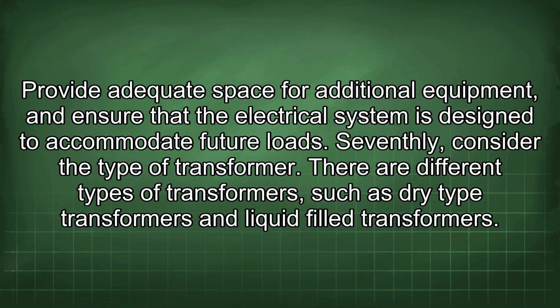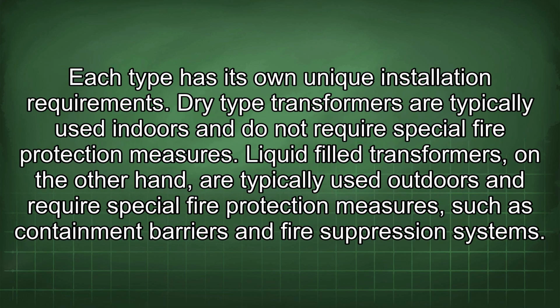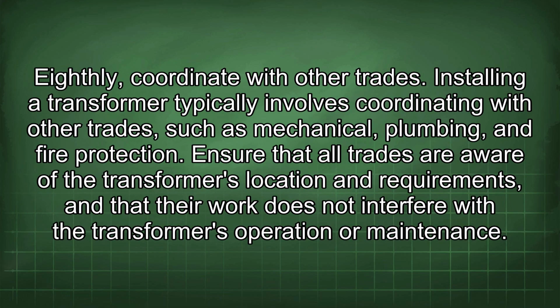Seventhly, consider the type of transformer. There are different types of transformers, such as dry-type transformers and liquid-filled transformers. Each type has its own unique installation requirements. Dry-type transformers are typically used indoors and do not require special fire protection measures. Liquid-filled transformers, on the other hand, are typically used outdoors and require special fire protection measures such as containment barriers and fire suppression systems.